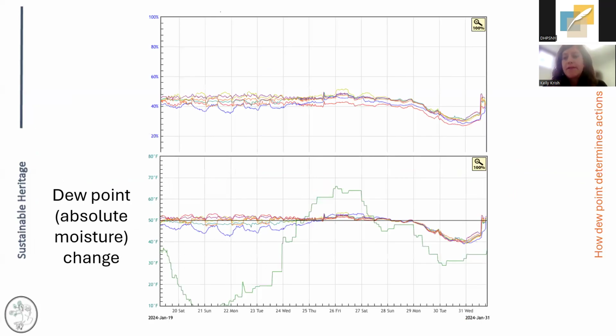So at the top, that's that first graph you saw of the relative humidity with the drop. And so we looked at dew point, and you can see that green line there is the outside air dew point, and you can see that it also dropped at that time. So what that tells me is that the moisture level changed, and we weren't able to counter that as we had been previously. And so it showed us that there was an issue with the humidification system, and we needed to look at that component, the humidifiers, and have those repaired.